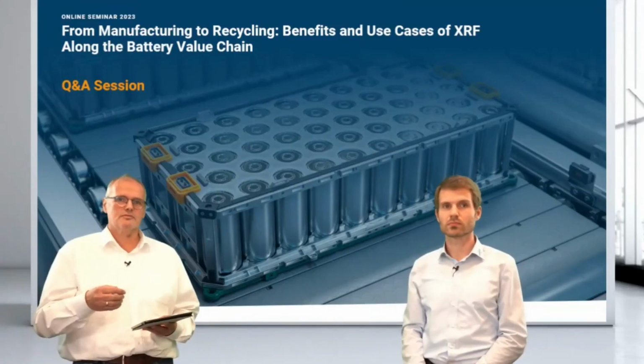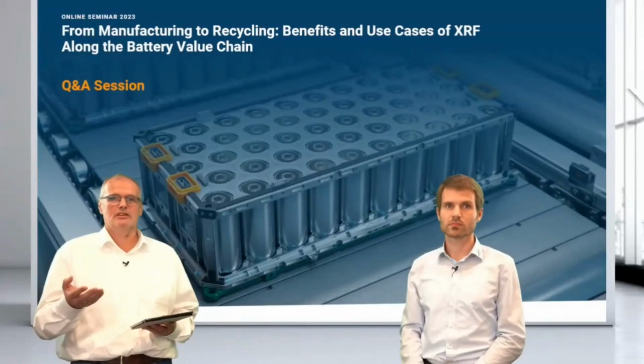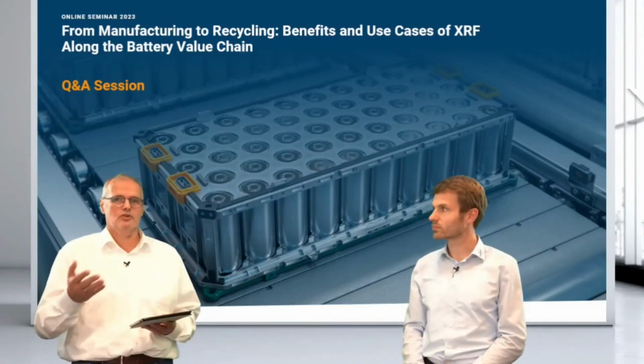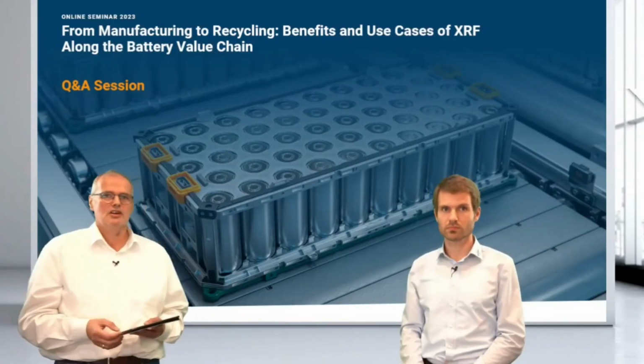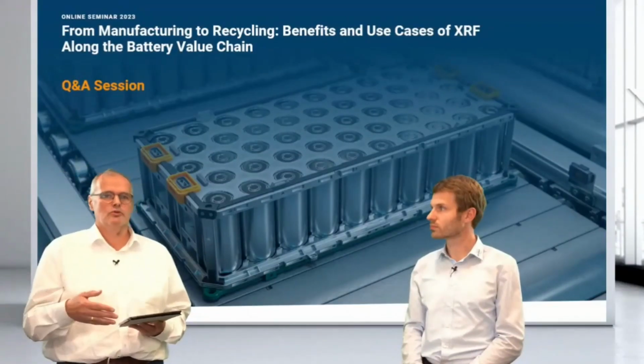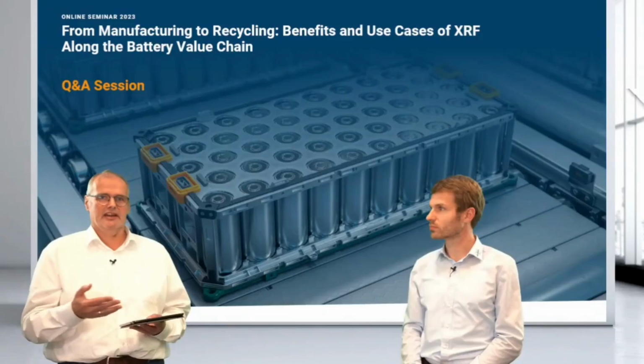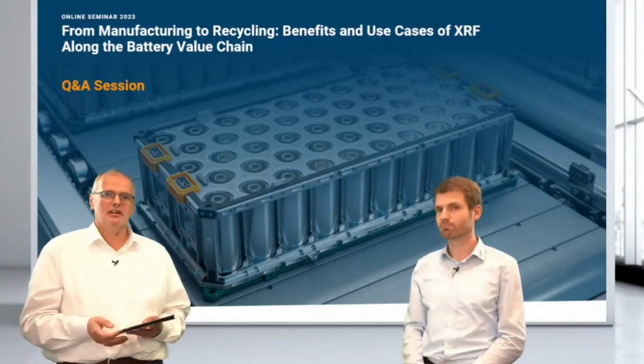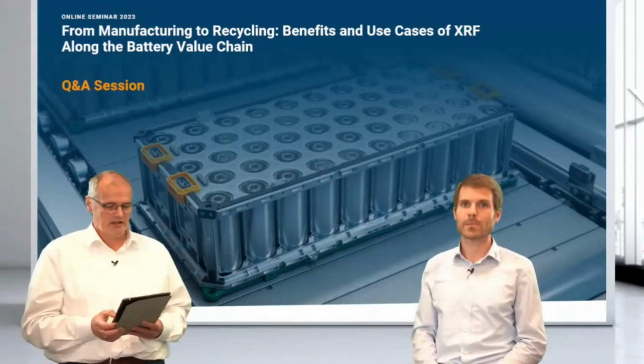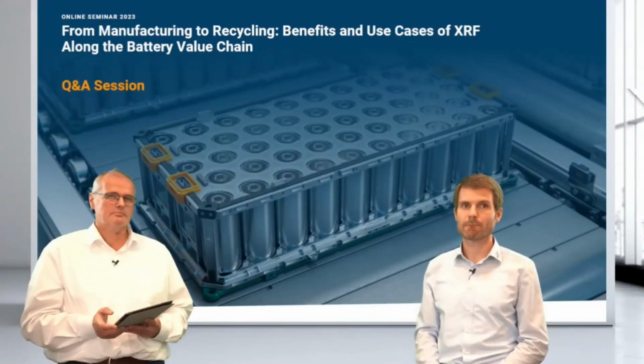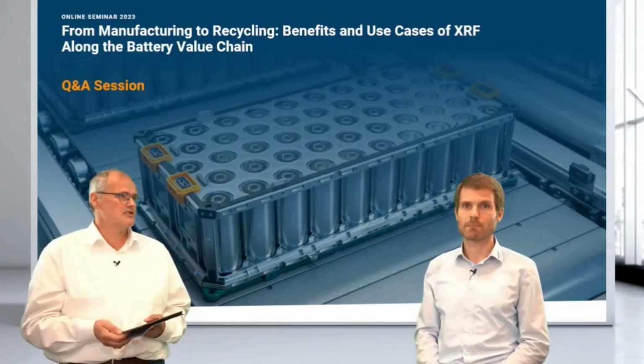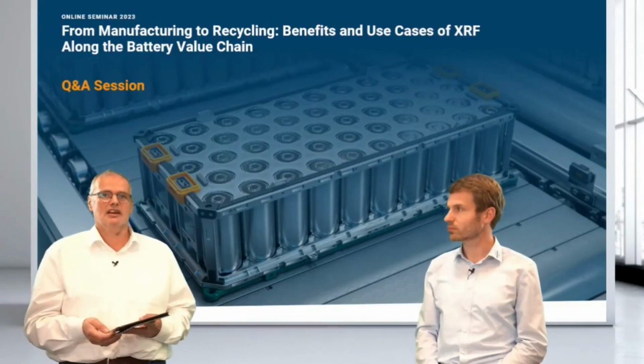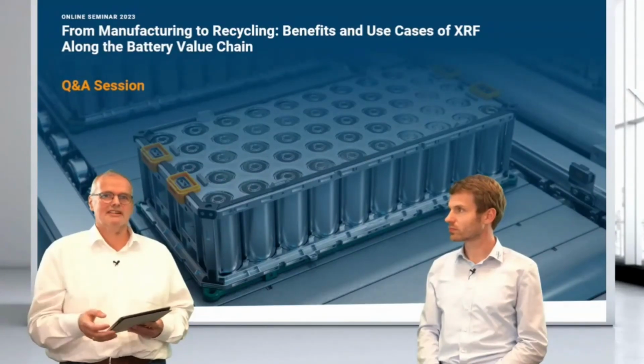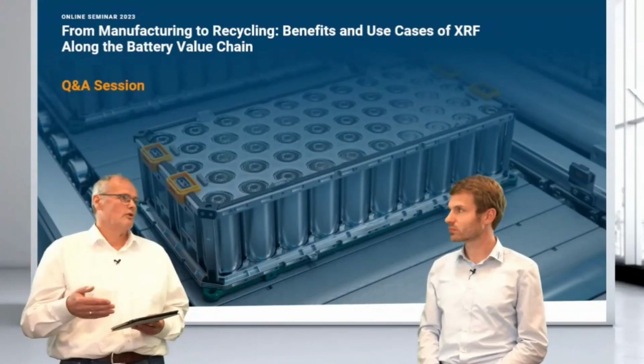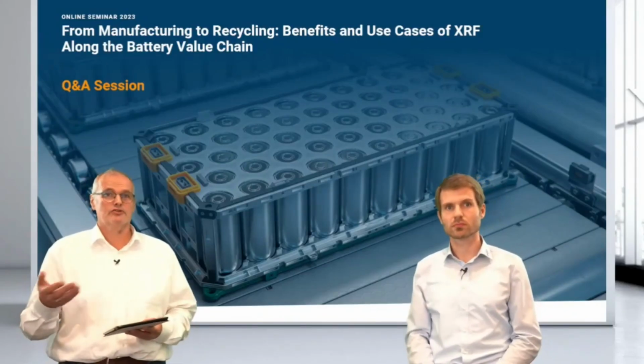And also, in terms of reaching a better accuracy or higher precision, the software can have multiple measurements for a single element in wavelength dispersive. So it would mean there's a setting for majors and a setting for traces, and then it uses the setting which is related to that count rate. Yeah. So there, XRF is pretty robust compared to liquid chemistry and doesn't need a digestion, as I said in my presentation. So actually, that's a big advantage when we are dealing with 100%, 50%, or traces.